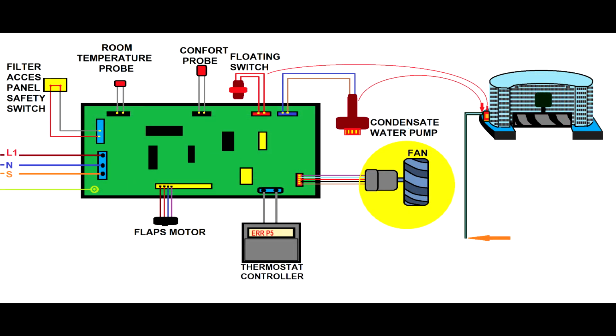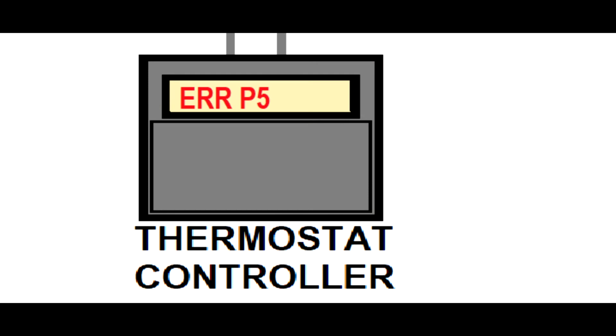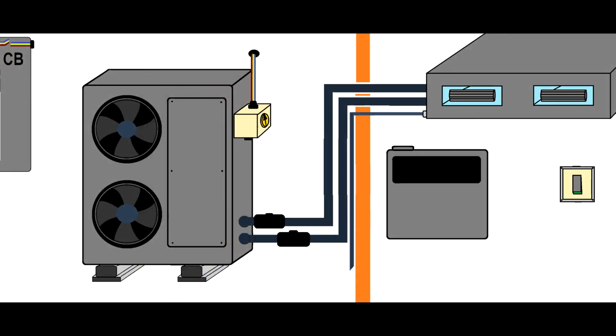See, you can see here much better now. If you have a fault on the pump or anything that is not eliminating the water, that floating switch will trigger an alarm, an error, P5. You have to reboot the unit, but then it comes back again.